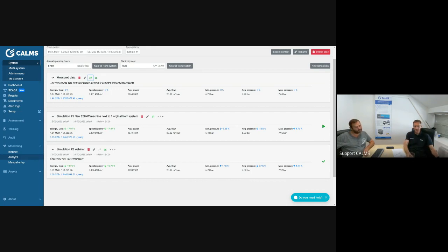What we have is the purchase of quite an expensive compressor to exchange a compressor that is still running, it's not broken. So the investment is quite high, but the return on this investment is also, I'm quite sure, quite short in this case. Further investigation in later chapters might find that there are options that are even cheaper to achieve almost the same outcome.